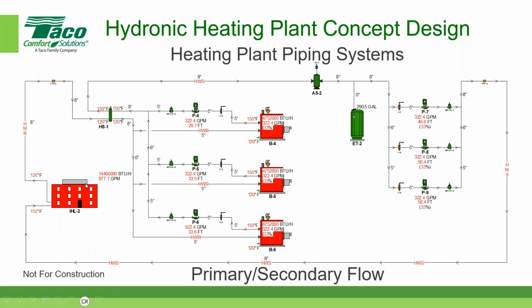So one of the nice features about primary secondary flow is that generally speaking, when you have a boiler running and its associated pump running, that pump and boiler combination is at constant flow. And so you don't have to worry about minimum flow through the boiler because it's at constant flow. And in this case, each boiler has a pump that's sized to 322 gallons per minute. That's kind of neat, huh? Yeah. Okay.